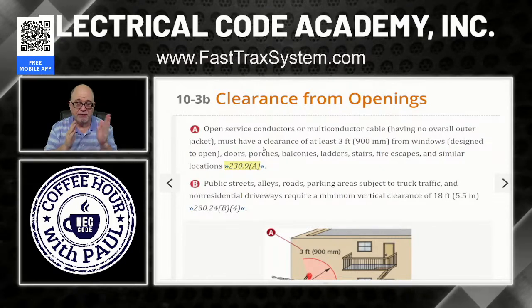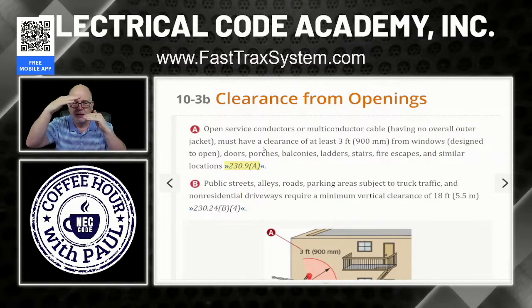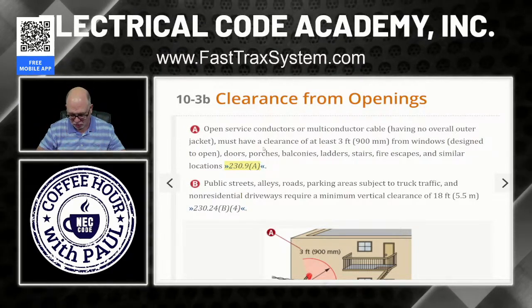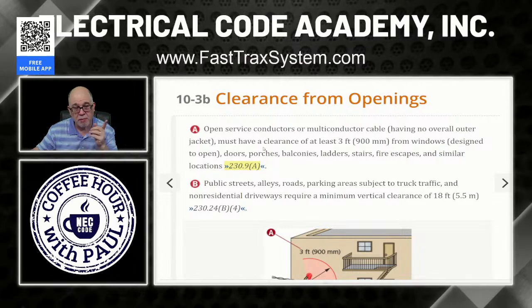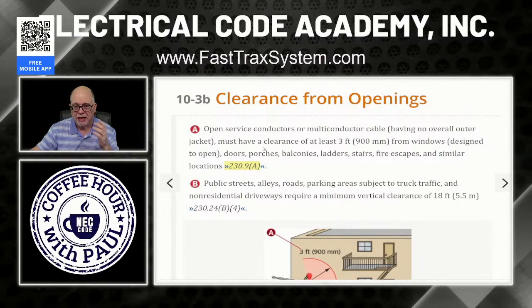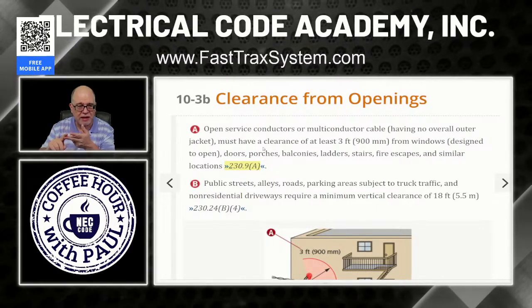It applies to the left of the window, to the right of the window, up to the very top of the window, but not above the window. And it also applies in front of the window and below. So it's 3 feet in all directions except for above the window. And remember, it does not apply to fixed windows that do not open. That same 3 foot clearance applies again to doors, balconies, porches, ladders, all that kind of stuff.